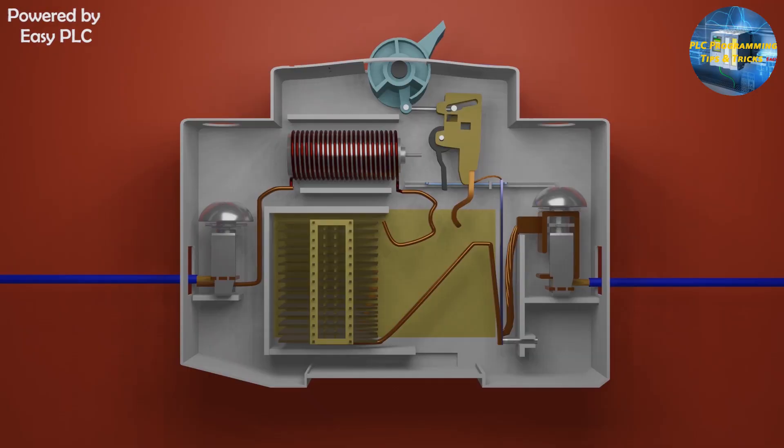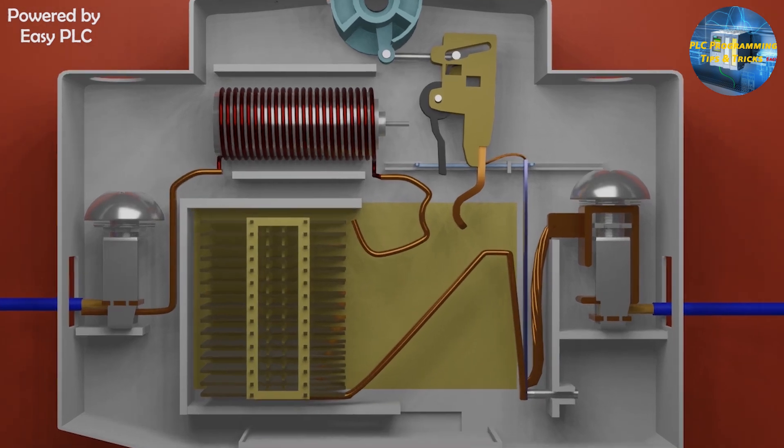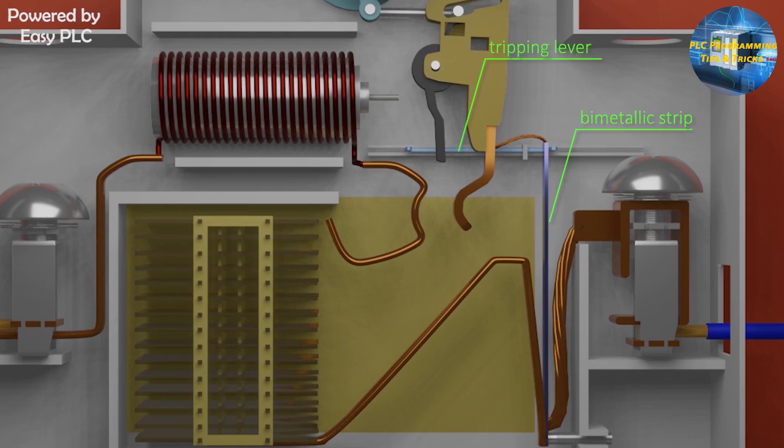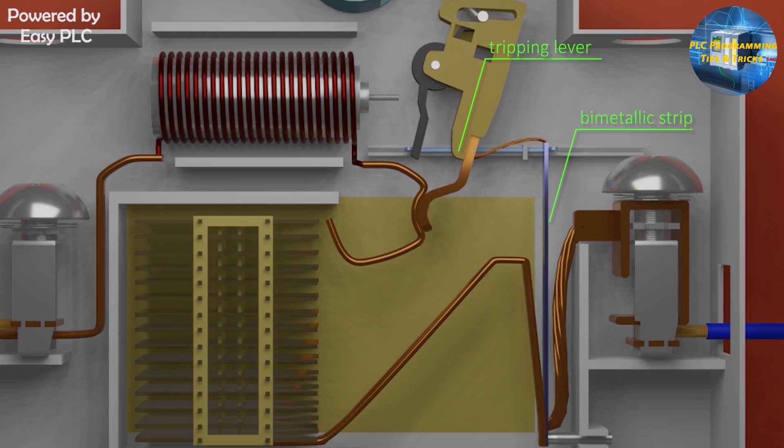Next we have a mechanism to trip the MCB in case of the overload current. This mechanism consists of two things: number one, bimetallic strip, and number two is a tripping lever. Bimetallic strip and the tripping lever work together as an overcurrent safety mechanism. When an excessive overload current passes through the bimetallic strip, this bimetallic strip gets heated and starts to bend.